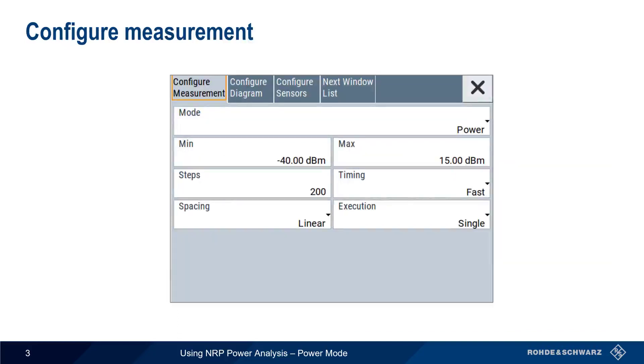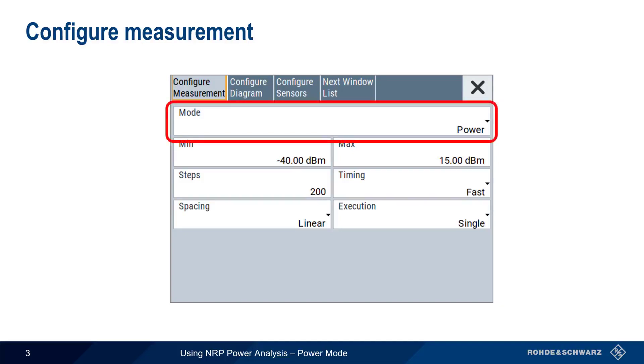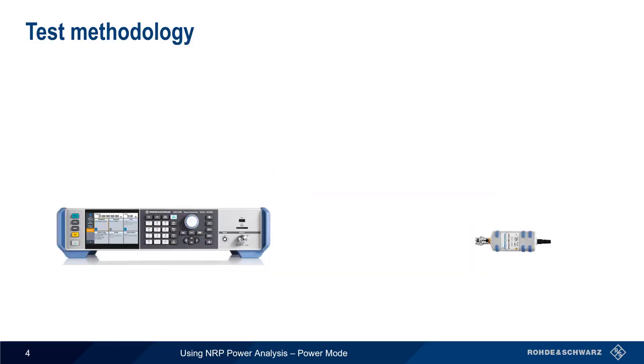In the frequency mode presentation, you should have already learned how to start the application and how to get to the Configure Measurement screen. The only difference here is that this time we'll be making a Power Mode measurement. In this presentation, we'll use Power Mode to determine the gain curve and compression point of an amplifier.